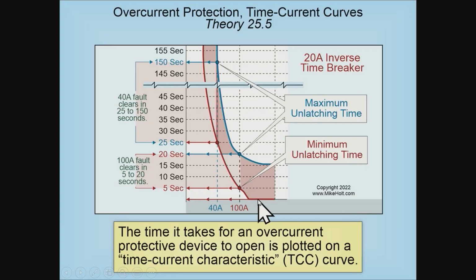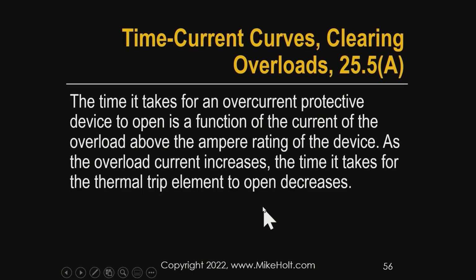Back to our time current characteristic curves. Some value that's pretty high in relationship to the rating of the protection device will take us into the instantaneous trip setting. And the time current characteristic curve is going to be different for every different type of manufacturer, different breakers. So let's just stop right there. That's what this chart is about. Now, let's see if it's right.